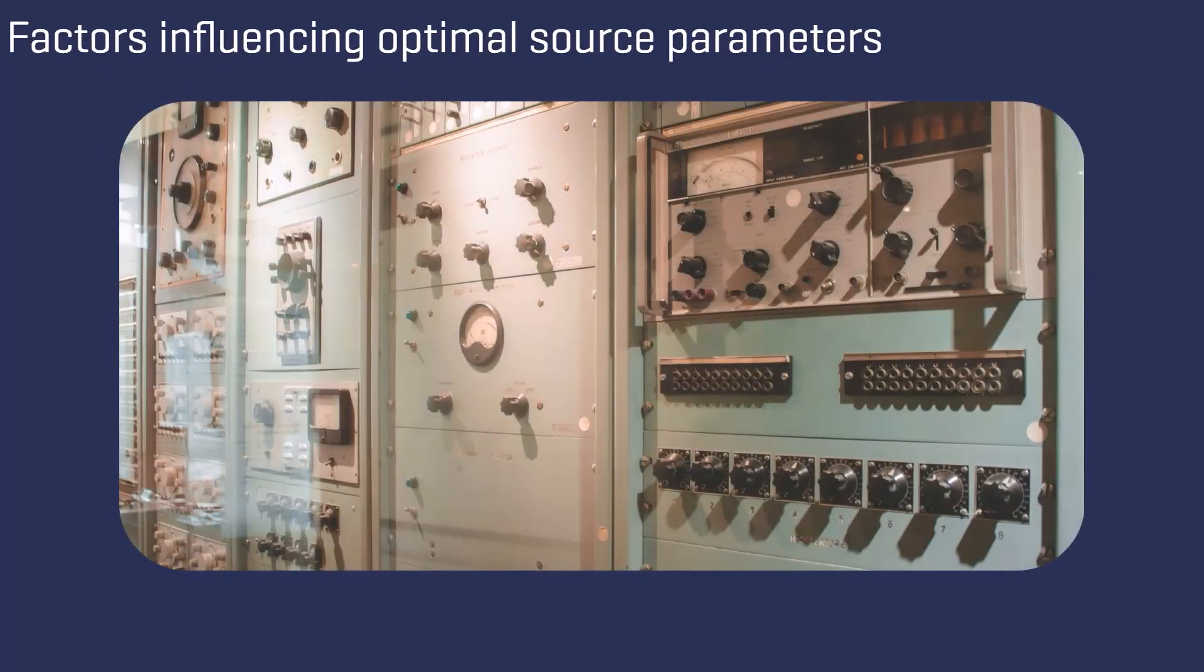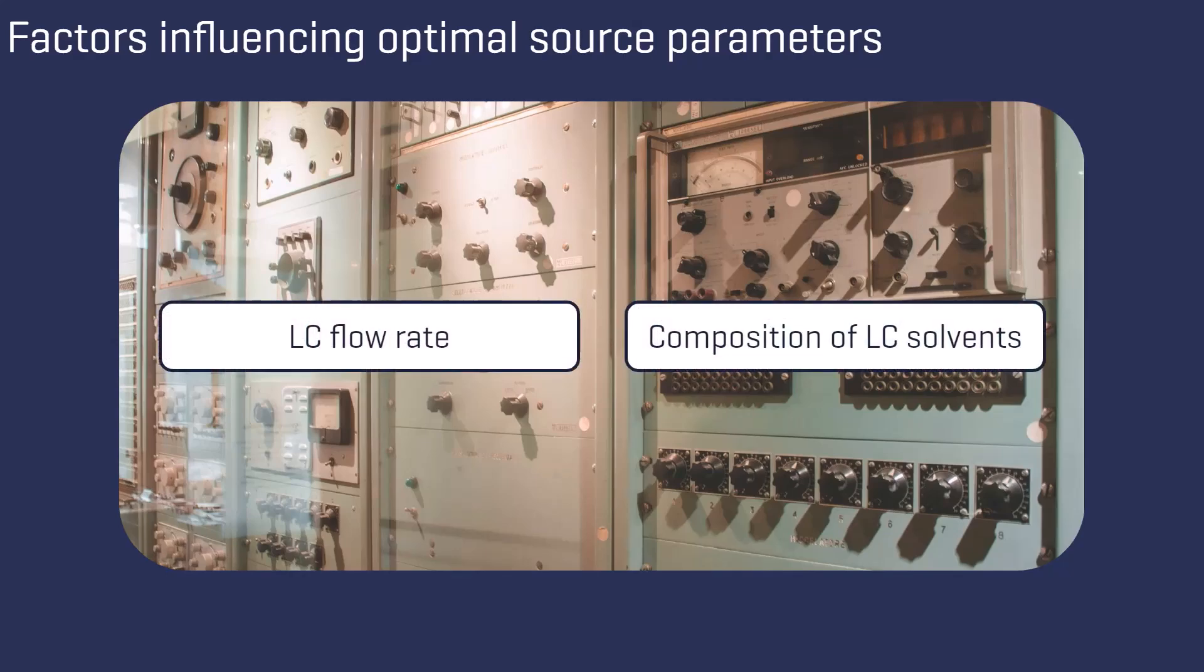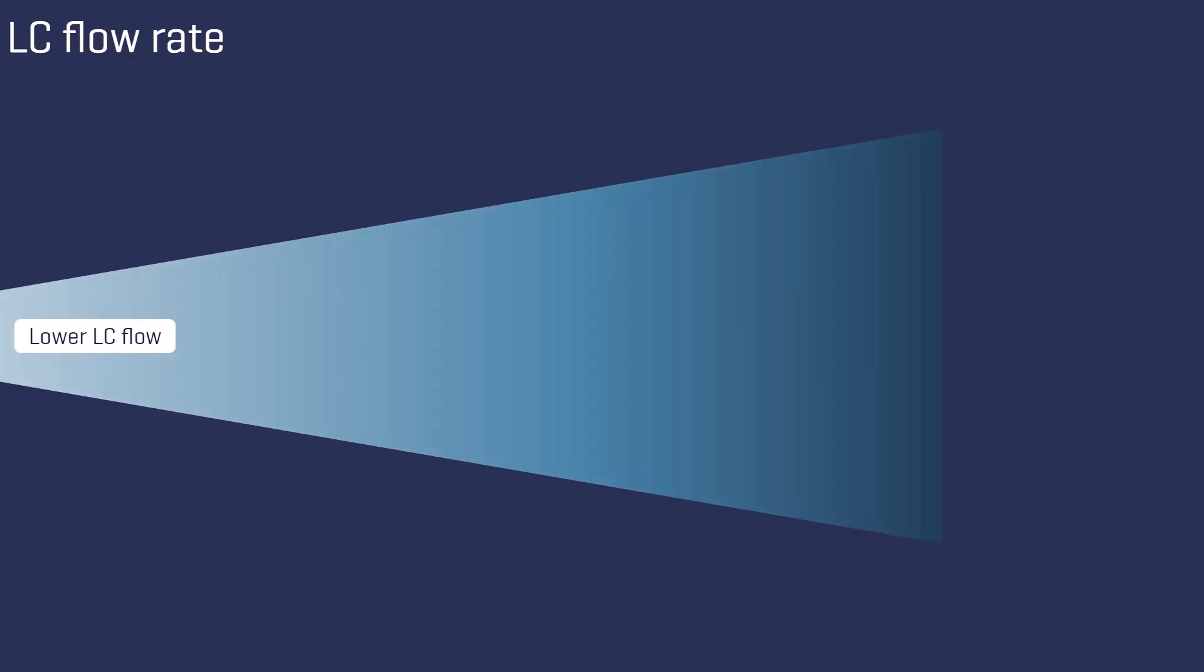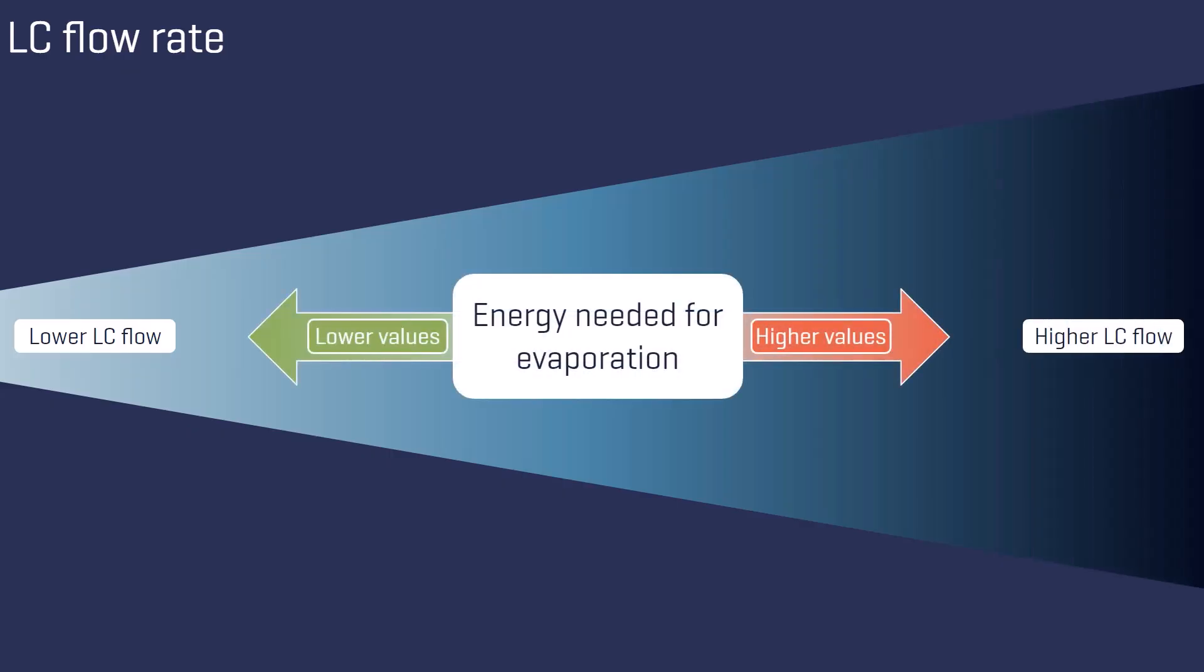What factors influence the optimal source parameters? They are mainly found in the flow rate and the composition of the LC solvent. As the LC flow rate entering the ion source increases, a greater amount of energy is required to evaporate the solvent.